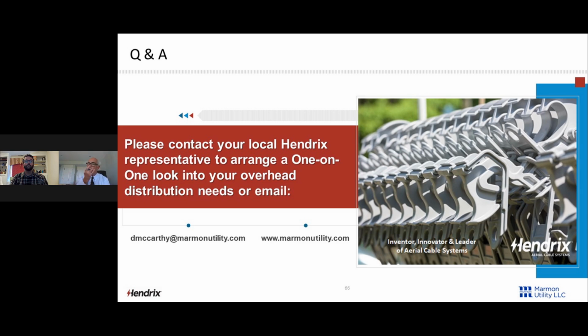What do you do? You clean off the ends. You wire brush the aluminum. You clean it off with a solvent. You put on the high voltage tape insulation, and we sell an insulated sleeve kit, so we have the instructions for that. Anybody that wants to know a little bit more about that can send me an email with your return email address, and I will give you complete instructions on tap making, splice making, et cetera, et cetera.